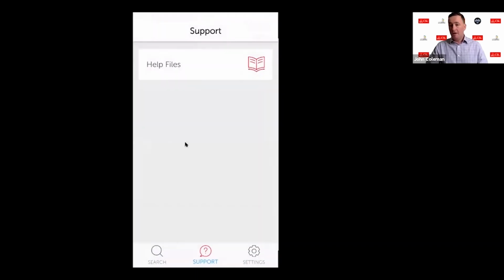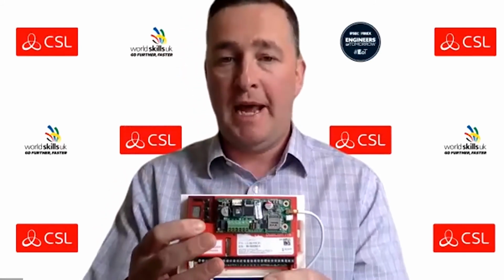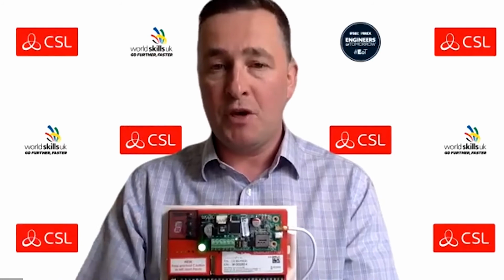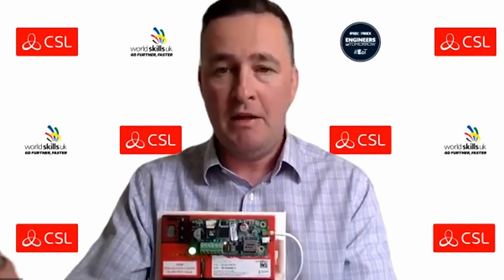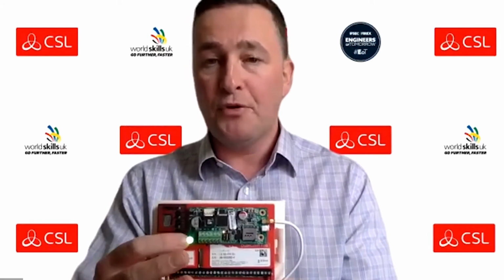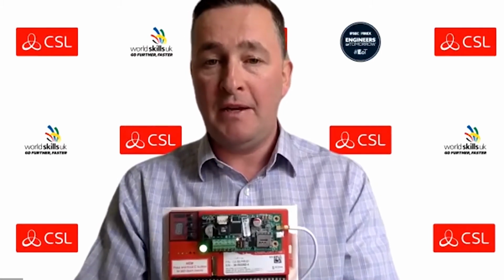For anybody that isn't doing serial connectivity and is continuing to do pin triggering, then what we've got on the DualCom Pro here are the A, B, and C buttons. So within 9 steps, you can actually program a device without using the app. So if you're still doing pins, just using channels and sending signals in fast format, SIA, whichever way it is that you're going to do, then again, by just using these 3 buttons here, you can get the device up and running. So if you want to learn the inputs, then quite simply what you would do is you press and hold button C, and then what you will then see is L appear on the display.